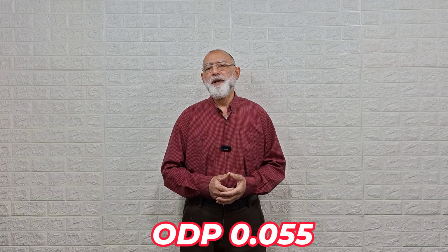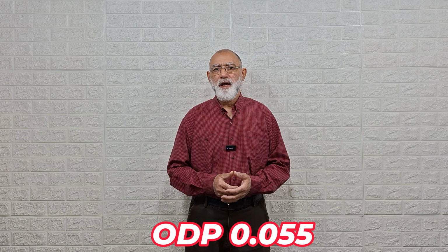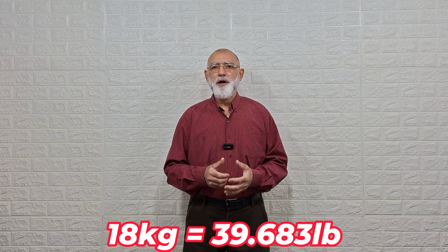Due to the damage this freon causes to the ozone layer, it was decided in the 90s to gradually replace it with new freons. The ODP, ozone depletion potential, of R22 freon is 0.055 compared to R11. That is, the damage caused by 18 kilograms of R22 freon to the ozone layer over a 100-year period is equal to the damage caused by 1 kilogram of R11.